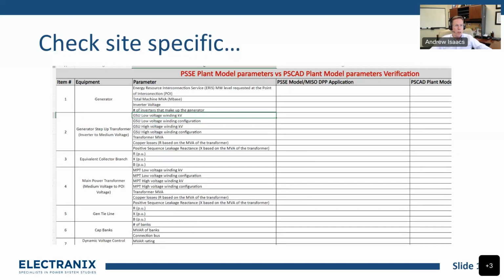Another spreadsheet checks the site-specific nature of the interconnection. So you have a generator, single line diagrams, specific machine MVAs, inverter voltages, generator step-up transformer winding kV and configuration, transformer MVA—all of these things should match in the PSSE model, they should match in the MISO DPP application, and they should match in the plant model. So you can go across here and these numbers should all be the same, right?